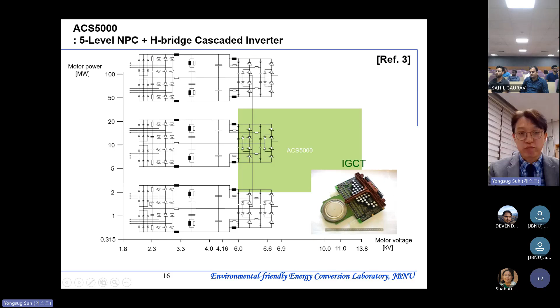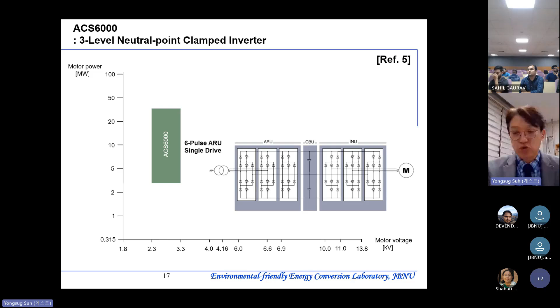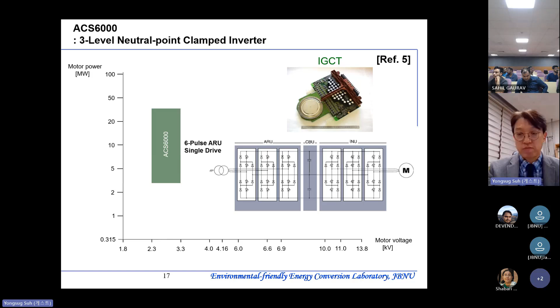You may have noticed that the topologies I covered a few minutes ago are all unidirectional, so we need a braking resistor to support bidirectional power flow. But ABB has the ACS 6000, also based on IGCT. This has an active front end, so bidirectional power flow can be achieved without requiring a dynamic braking resistor. The ACS 6000 is heavily used in electric ship propulsion systems.